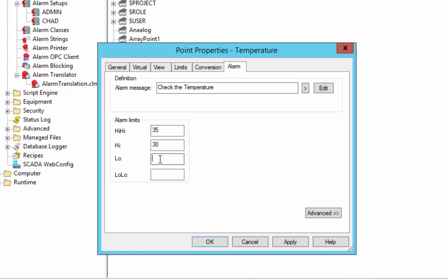We also want to say that if the temperature starts getting too low on our sensor, that we want to be warned as well. So let's say minus 5 is getting a little bit worrisome, and even more worrisome is if it gets below minus 15. So this sets up the parameters by which the runtime will specify that this value is in alarm.